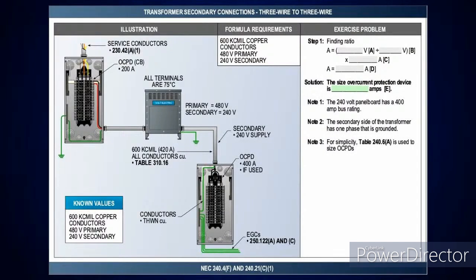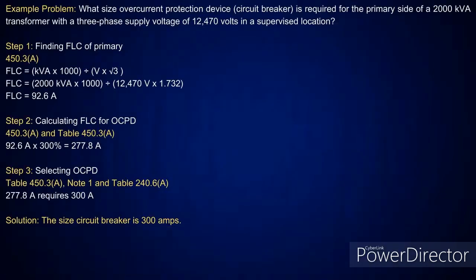How did I take here on this secondary and allow a 400 amp overcurrent protection device? Well, we're showing you the conductors are good for 420 amps. So I'm just going to take the 240 volts, divide the 480 into it, take the 420 amps, and then size your overcurrent protection device. With that right there, we're going to stop, and then we'll get into the transformers next week, really breaking down and showing how to size the overcurrent protection device.